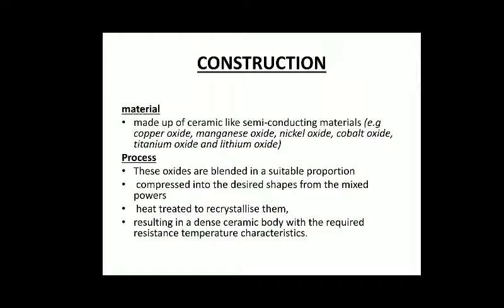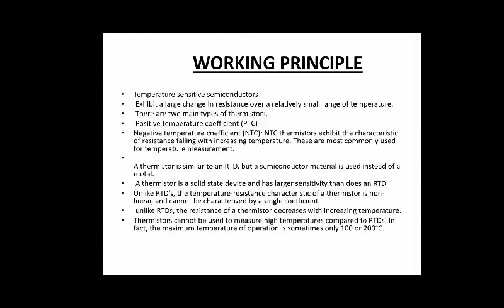Thermistors are made of ceramic-like semiconducting materials such as copper oxide, manganese oxide, nickel oxide, cobalt oxide, titanium oxide, and lithium oxide. These oxides are blended in a suitable proportion, compressed into desired shapes from mixed powders, then heat treated to recrystallise them, resulting in a dense ceramic body with the required resistance-temperature characteristics.